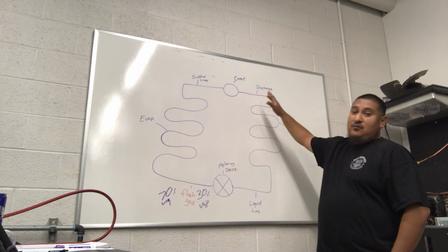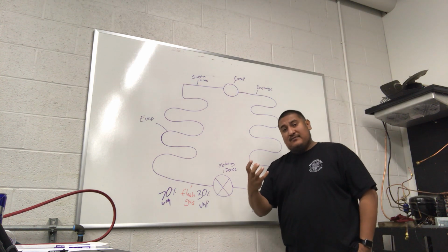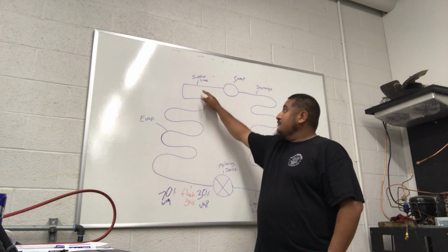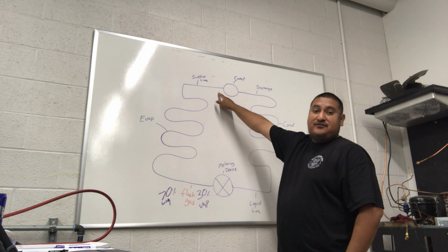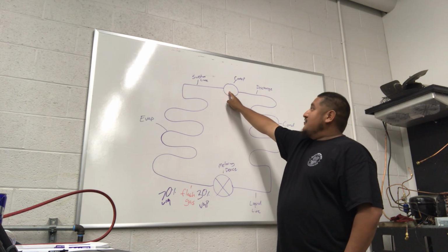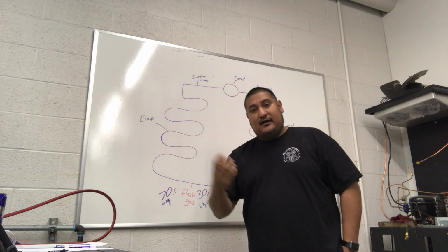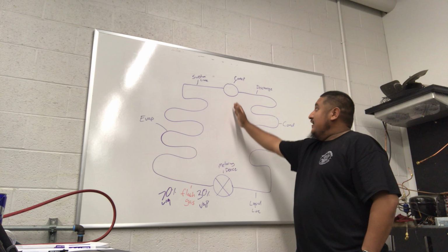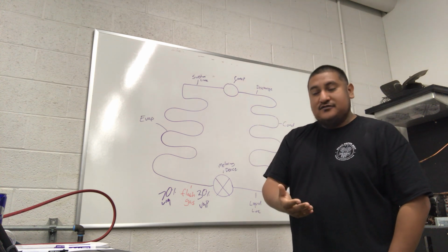Well, now we're going to have a little bit more liquid now, right? Well, now we have to start to add stuff that's going to trap that liquid. Because if you send too much liquid on this guy here, you're actually going to have liquid that's going to start to make its way back into our compressor, right? You guys have to understand again, this compressor is nothing more than an air pump. All it does is suck in gas. That's all it wants is gas.